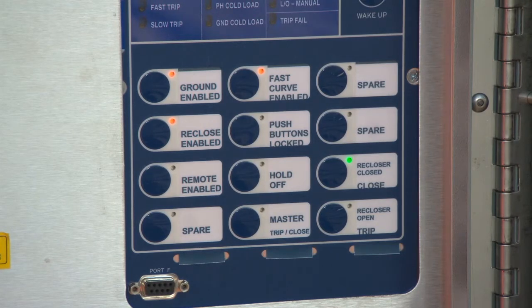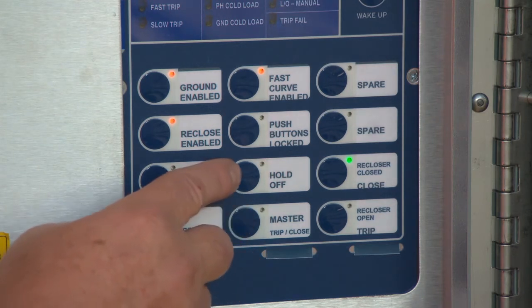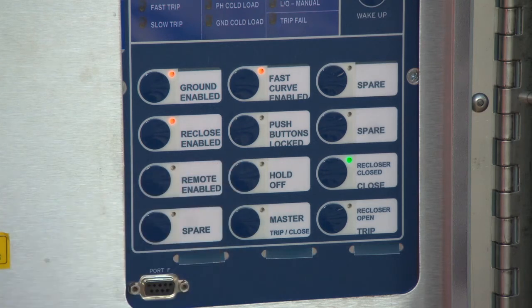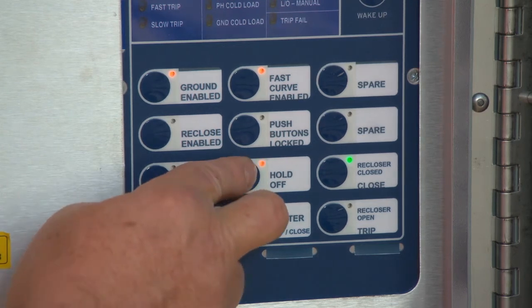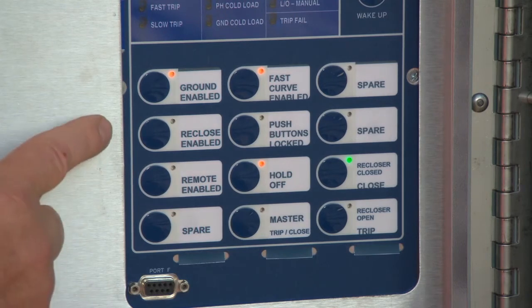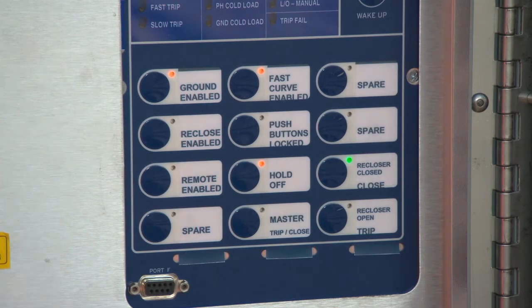Hold off. This is the American term for our hotline tag. To activate the hold off requires a 2-button operation. Push and hold the master button while also pressing the hold off button. When the hotline tag is enabled, the recloser will execute a single fast curve to the final lockout state. The Reclose Enable indicator LED will turn off, confirming that a single shot to lockout will occur.